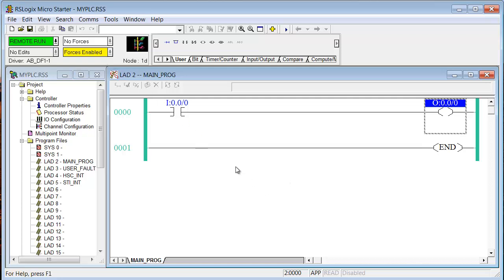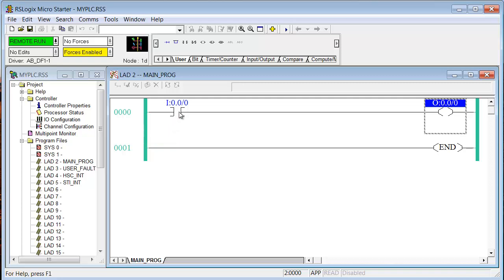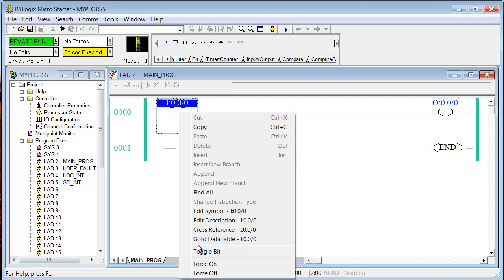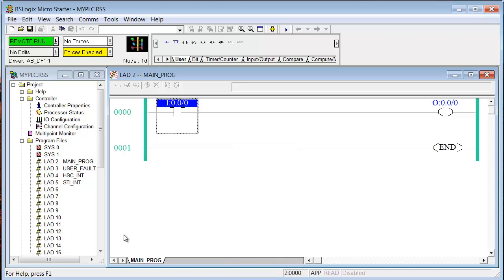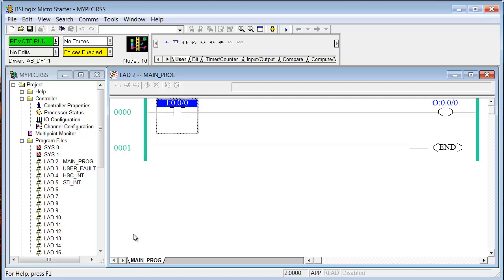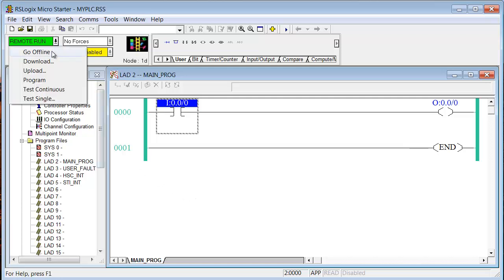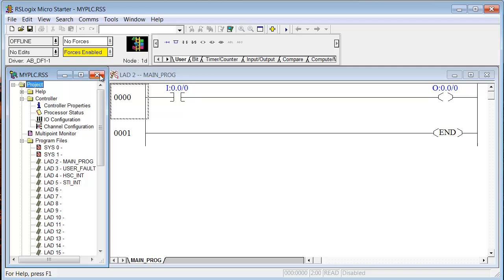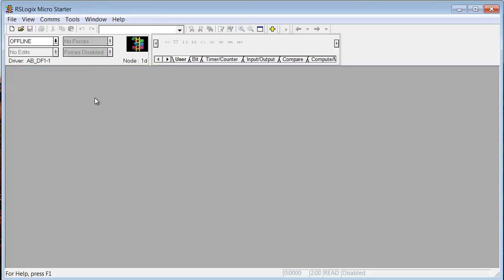Now since this processor does not support online programming, there's real no value in saving from online unless you want to save your data table. In other words, if you had a timer in there, well, we can't edit online. So we can't change anything to demonstrate. But if I were to toggle this bit on with a switch, now that bit is on in memory, I 0.0 slash 0. That bit is on, and the bit O colon 0.0 slash 0, it's also on. That means your data table values have changed. If I click it off, they've changed back. So there's really nothing to save from this type of a processor unless you had a program in here that had data that was being manipulated, integers, math, and things like that. In this case, saving was of no real value, so we might as well just click and go offline. We saved this, so I can click here to shut the program down. Now there's no program open.